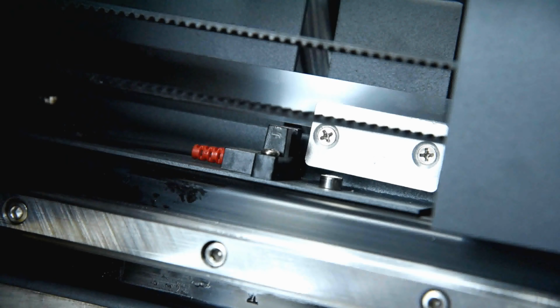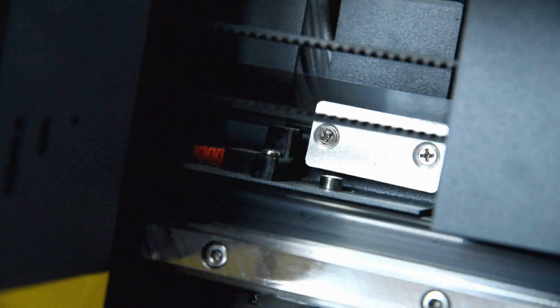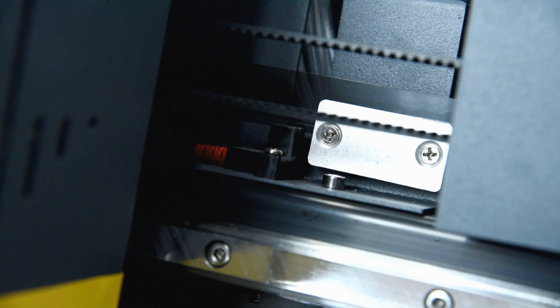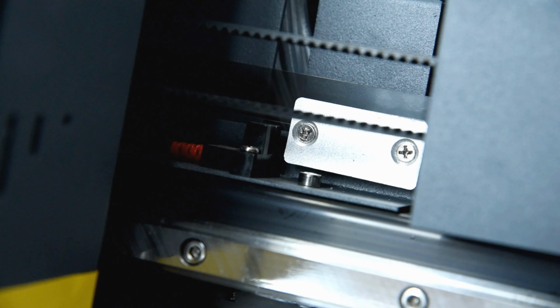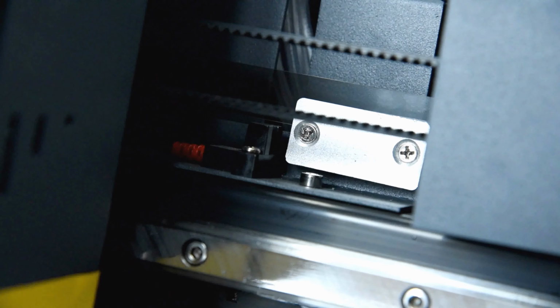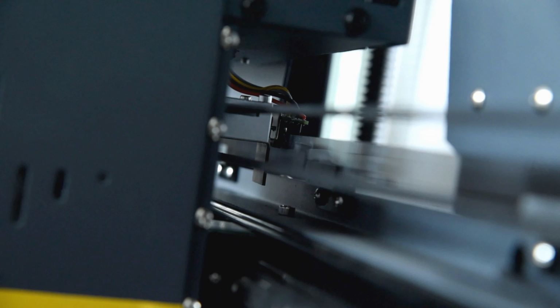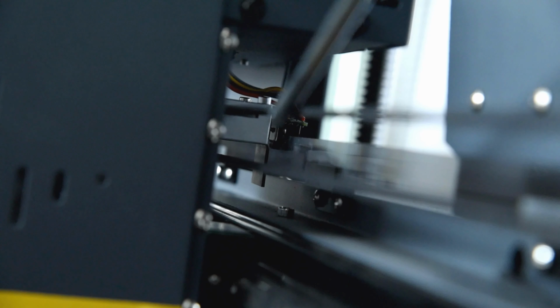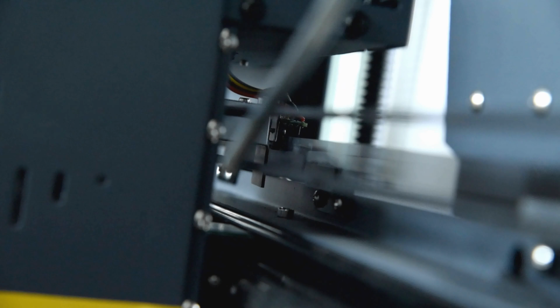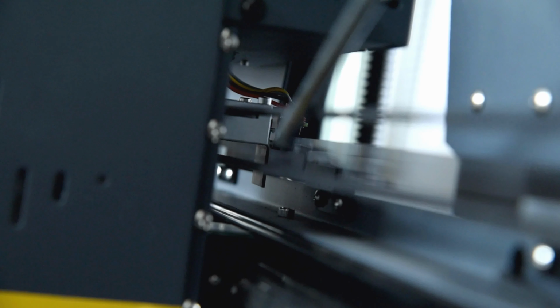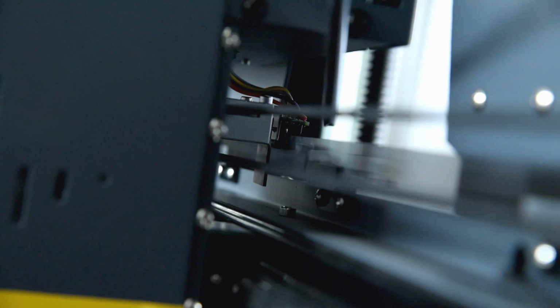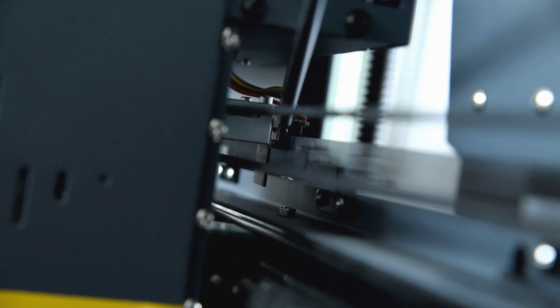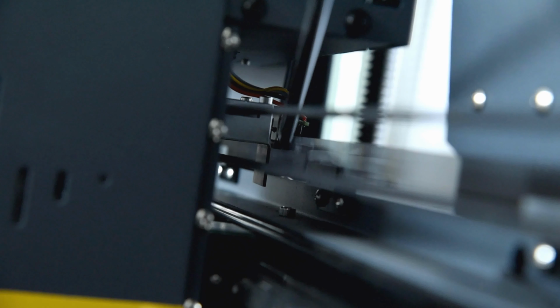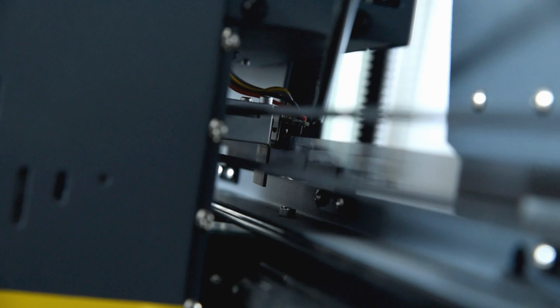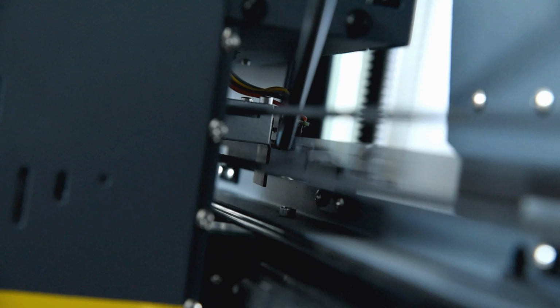And this is the home limit sensor to protect the carriage from moving out of the home position. When it moves to the right, the sensor detects the metal at the bottom of the carriage to protect the print head and the carriage from moving out of the home position. And when we go to the bottom of the carriage, we can see there's the ink film and the ink sensor here. And we must be sure the film, this is the film, this is the sensor. And it must be sure the ink film stays in the middle, left and right, up and down, at the middle of the sensor.